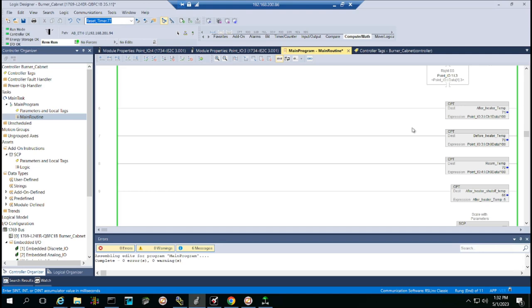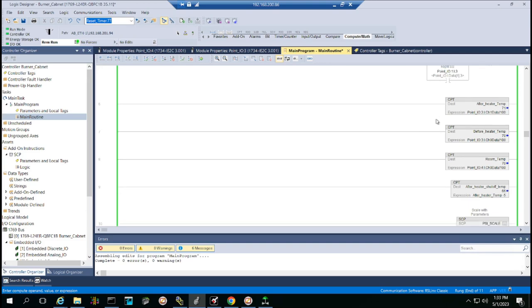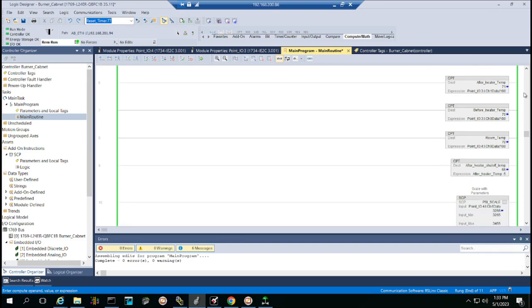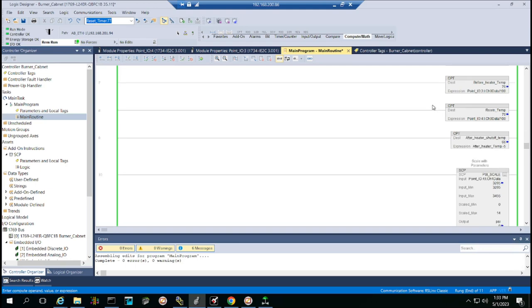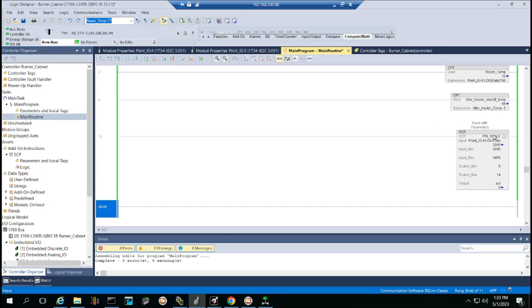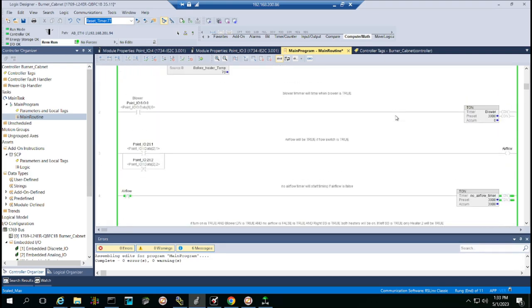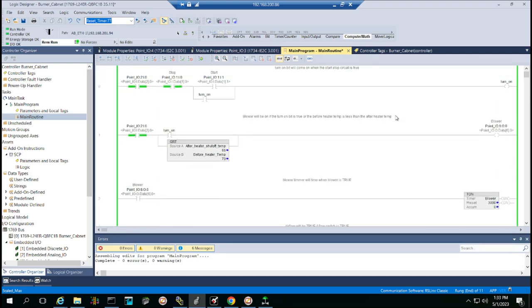So, and then the rest of this program is just compute instructions, just dividing our raw data we get from our temp probes by 100 to get these degrees in Fahrenheit to make it more readable. And then I have a scale with parameters for my pressure sensor to get the correct PSI. But that about wraps it up.